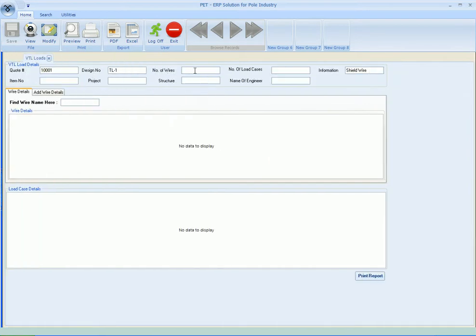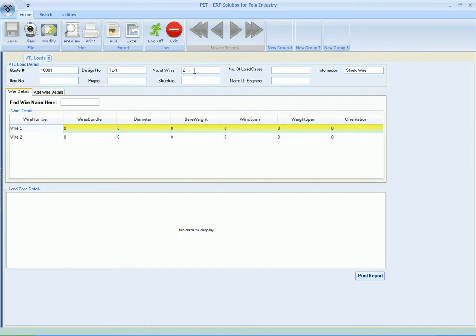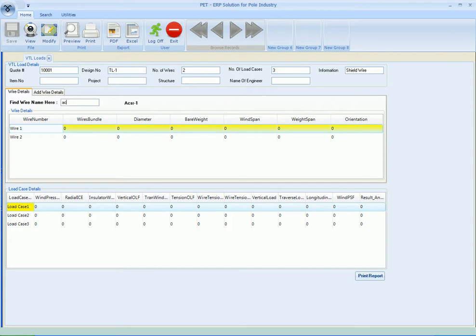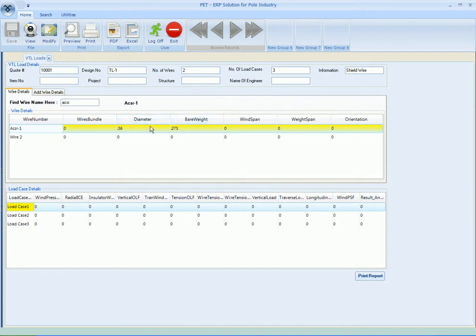Number of wires is two, number of load cases let's say three, at the shield wire position. Now we will have to enter for the first wire - wire name like ACSR. It suggests you the related wire names. If you press the tab it will give you the bare diameter, bare weight, and the wire name.